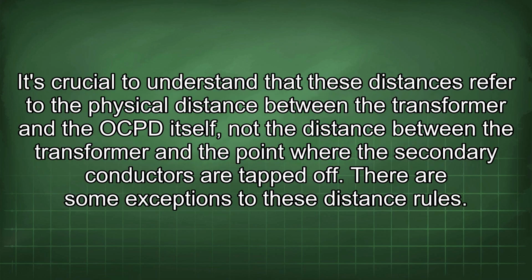It's crucial to understand that these distances refer to the physical distance between the transformer and the OCPD itself, not the distance between the transformer and the point where the secondary conductors are tapped off. There are some exceptions to these distance rules.